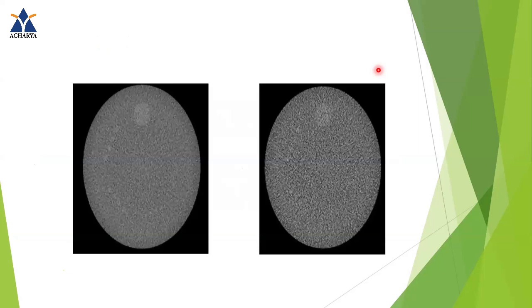This is how the image resolution varies with variation in the MAS. This is the image with high MAS and low MAS. With low MAS, the number of X-ray photons reaching the detector is less, so the image will be grainy. Whereas with higher MAS, the number of X-ray photons reaching the detector is more, so the image resolution is very high. But when we increase the MAS, the radiation dose also doubles.